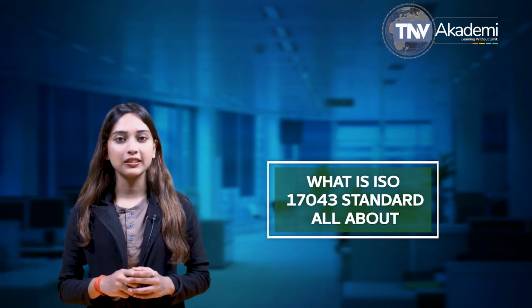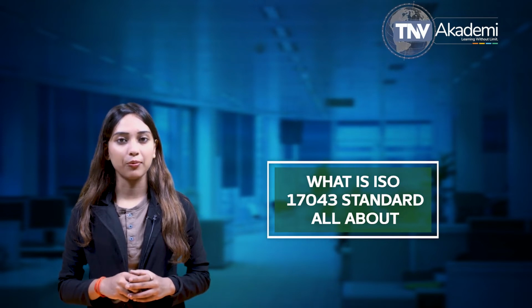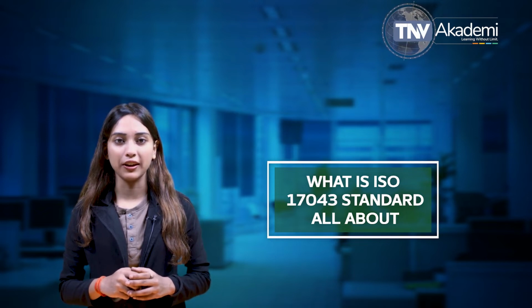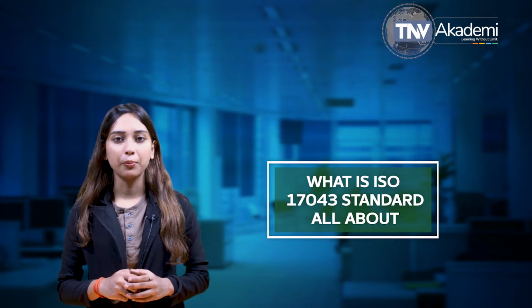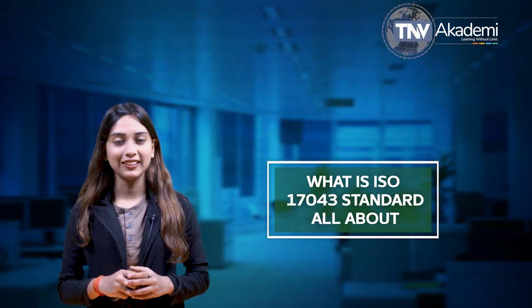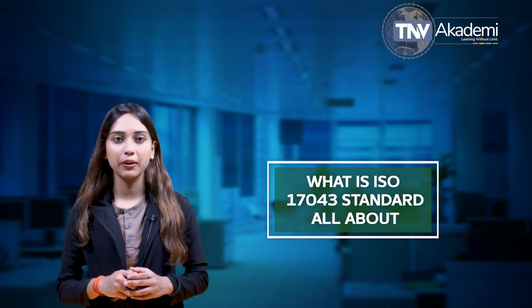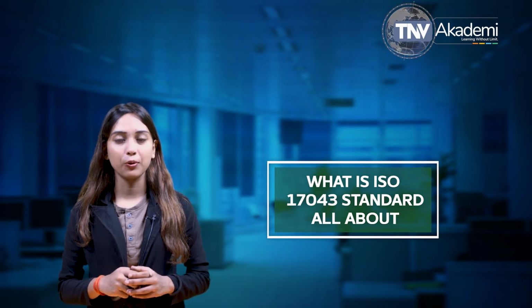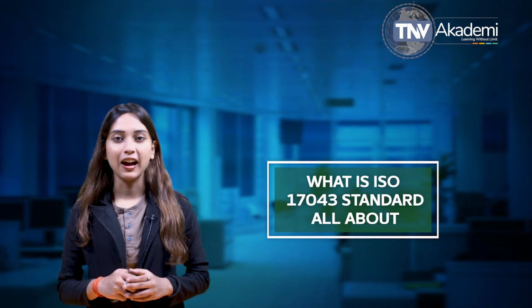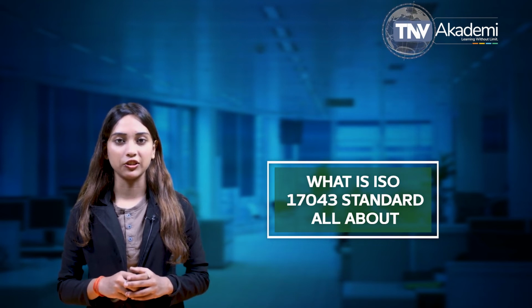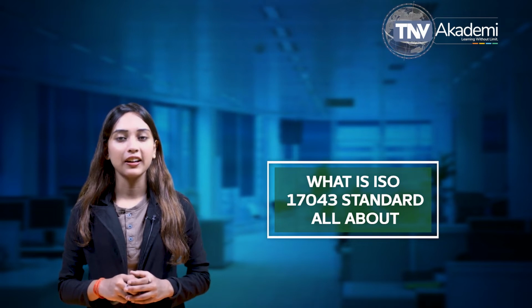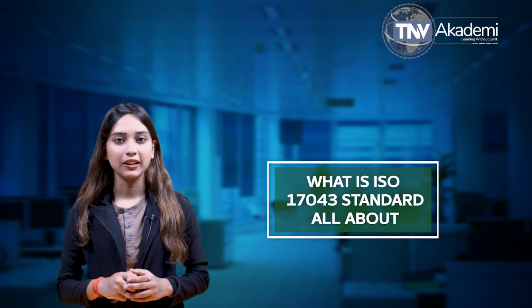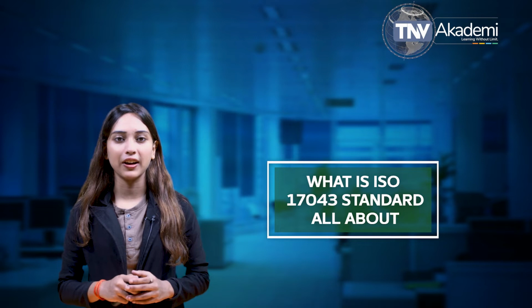Proficiency testing addresses these 7 requirements. First, the performance of laboratories for testing or measurement and monitoring a lab's performance. Second, identifying problems in the lab and initiating action for improvement, for example inadequate test or measurement procedures, effectiveness of staff training, and calibration of equipment. Third, the establishment of effectiveness and comparability of test or measurement methods. Fourth, the provision of additional confidence to customers. Fifth, identification of interlaboratory differences. Sixth, education of participating laboratories based on the outcome of these comparisons. Seventh and last one, validation of uncertainty claims.